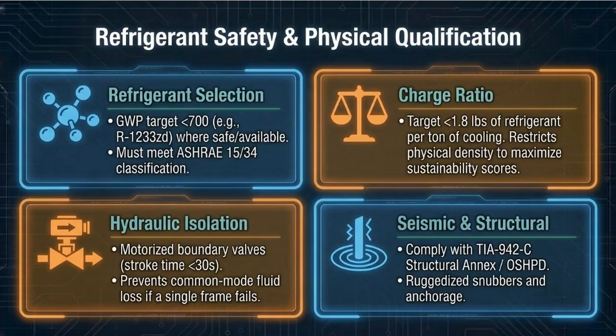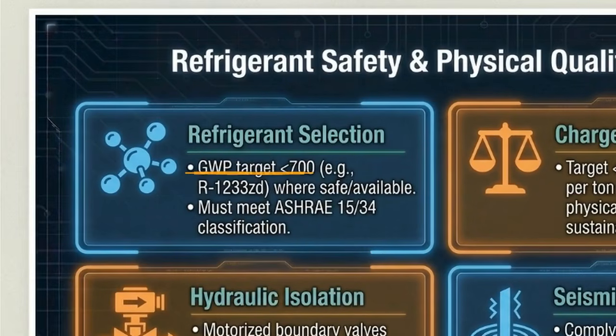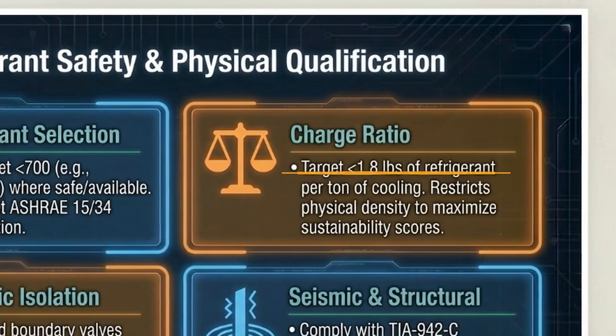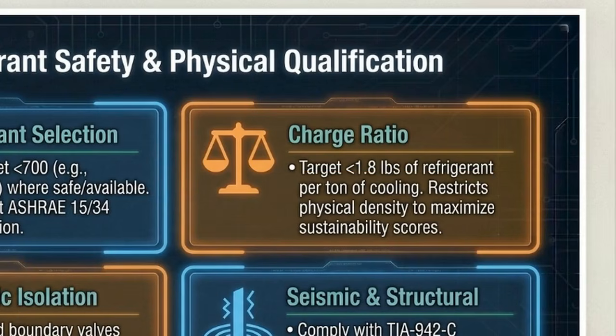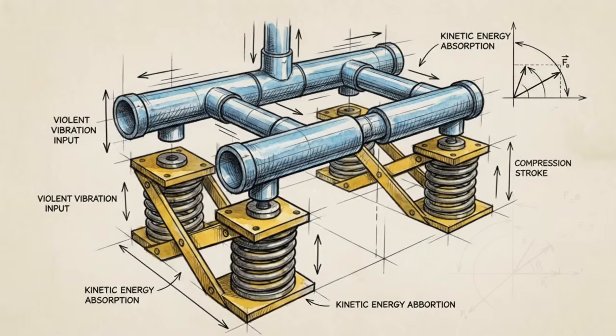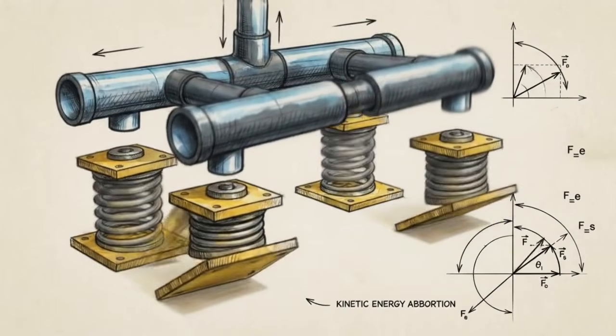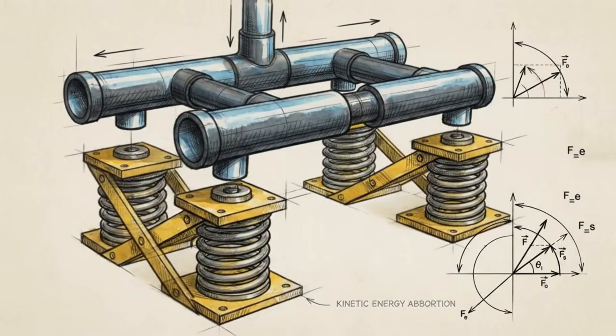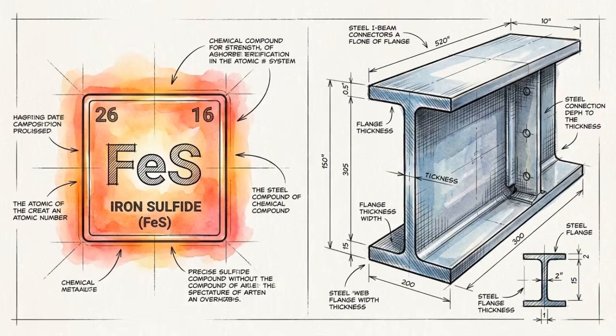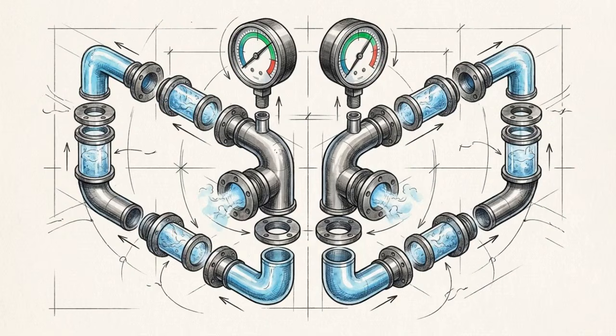Detailing physical qualifications, this chart shows environmental restrictions on refrigerants, guided by LEED baselines. Targets require utilizing refrigerants with a global warming potential below 700 and strictly limiting the charge ratio to less than 1.8 pounds per ton of cooling capacity, maximizing sustainability. Containing highly pressurized refrigerant requires serious physical infrastructure, including certified seismic bracing to ensure violent structural shifts during an earthquake do not fracture critical lines. Sustainability is a chemical and structural engineering problem. Efficiency targets hold value only if the fluids driving them remain mathematically balanced and safely contained within the pipework.